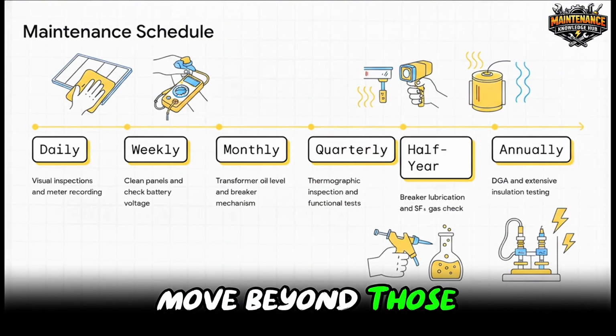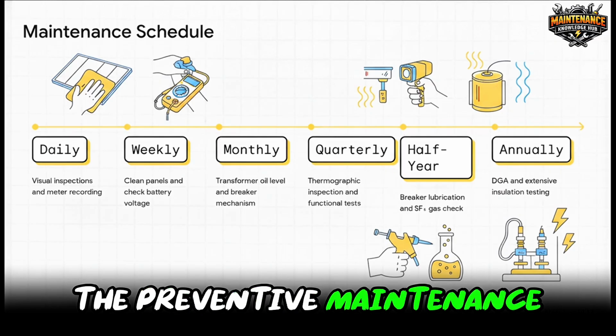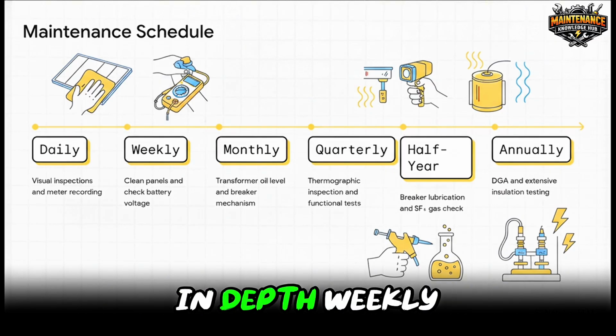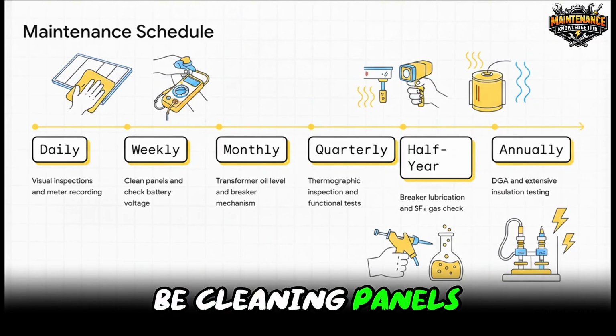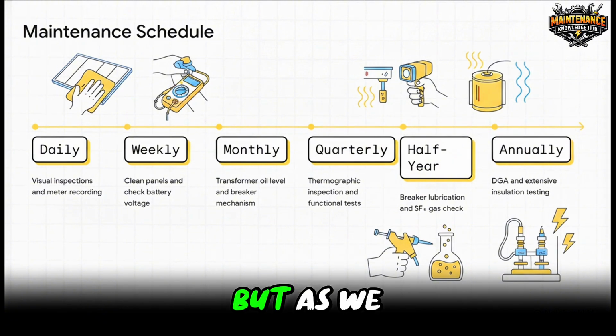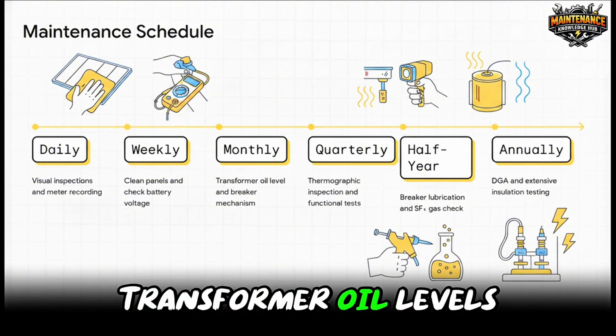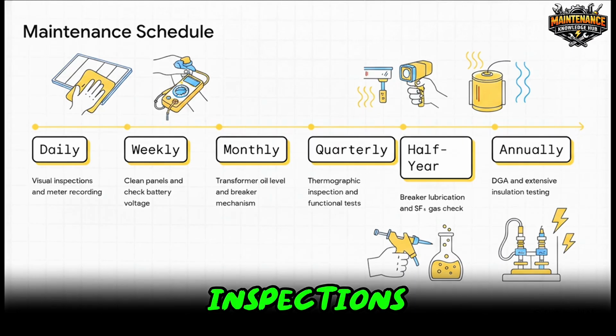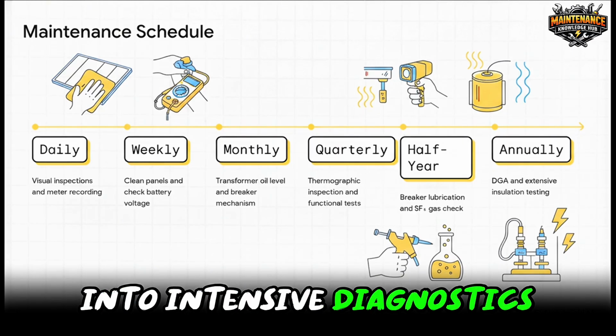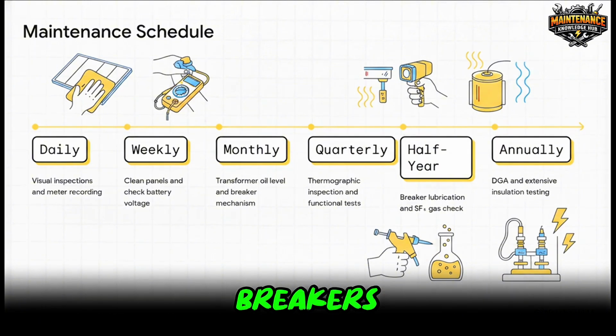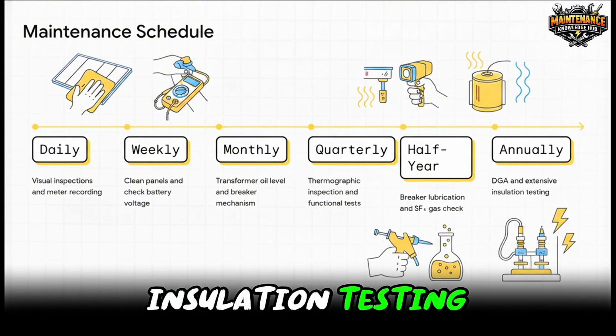Now, as we move beyond those daily checks, the preventative maintenance schedule really scales up in depth. Weekly tasks might just be cleaning panels or checking battery voltages. But as we get into the monthly and quarterly schedules, we start inspecting transformer oil levels and doing thermographic inspections. And by the half-yearly and annual marks, the work shifts into intensive diagnostics. We're talking lubricating breakers, running a dissolved gas analysis on the oil, and performing major insulation testing.